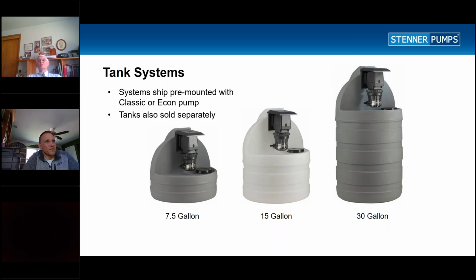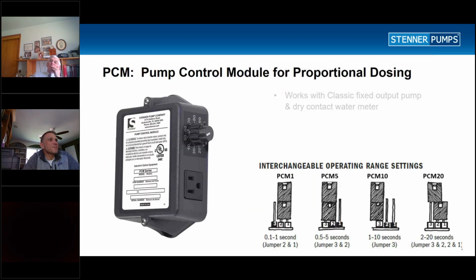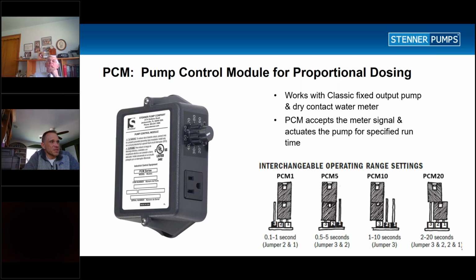Accessories. We do offer the solution tanks with the ability to mount the pump onto the tank in 7.5, 15, and 30-gallon versions. You can also purchase the tanks separately if you need. The pump control module, which I mentioned, this is the unit in which the classic pump would connect into. So you would plug the classic pump in here, and then where your feed rate control would normally be on the pump is now taken over by a switch on the side of the feed rate control. And your flow is then determined based off percentage and runtime, depending on the chemicals that you're dispensing.